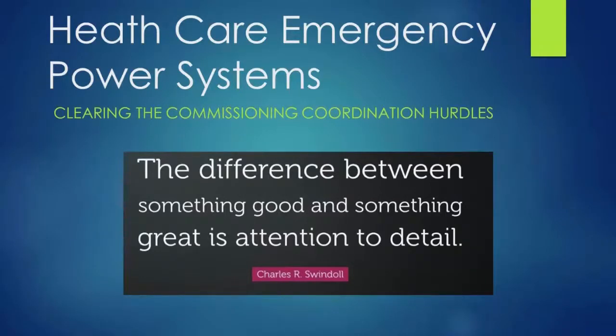We look at how it transitions between loss of normal power and back onto emergency power, and then from emergency power back to normal. In those instances we would have the BAS vendor, mechanical and electrical facility staff, a mechanical commissioning agent, and an electrical commissioning agent. We would visit every piece of equipment. Before the test, we'd document all the equipment we expected to be interrupted and impacted, then physically view each piece of equipment to make sure it made that transition correctly in both directions, so we could report to our client how the system worked and what issues need to be corrected.